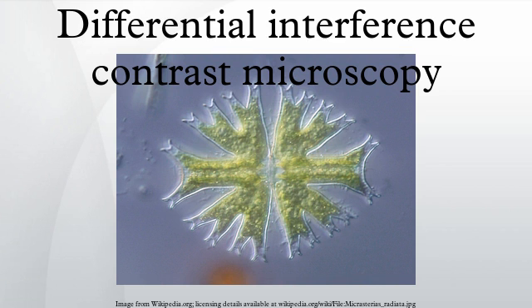The image has the appearance of a three-dimensional object under very oblique illumination, causing strong light and dark shadows on the corresponding faces. The direction of apparent illumination is defined by the orientation of the Wollaston prisms. The image is generated from two identical bright field images being overlaid slightly offset from each other, and the subsequent interference due to phase difference converting changes in phase to a visible change in darkness. This interference may be either constructive or destructive, giving rise to the characteristic appearance of three dimensions. The typical phase difference giving rise to the interference is very small, very rarely being larger than 90 degrees.